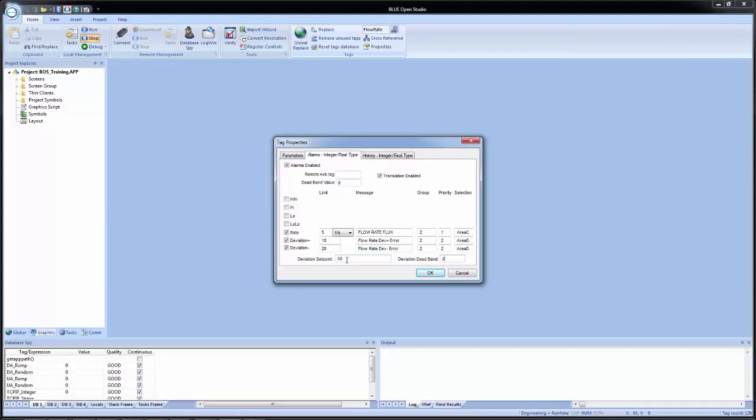So for example, if we have a deviation plus alarm, when the value comes back down, it can't get to, say, 60 and then 59. And once it hits 59, the alarm would normally be recovered or normalized. With a deadband configured, it now has to drop all the way down to 52 in order to normalize. And the same for the deviation minus. For us, we're just going to leave the set to 0. And then we are going to click OK.